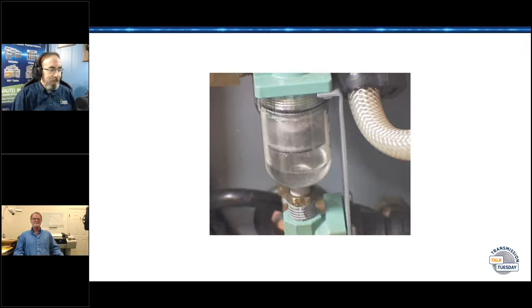Getting back to dehydrators and line, occasionally we do discover - and I noticed none of these are 22 caliber size holes, which are the ones I tend to encounter the most - but lightning, forklifts... I had one site, for example, where they had 3 lengths, I think it was 600 feet of 3 1/8 line delivered, before they got one that wasn't received punctured. So that's definitely something you look at.